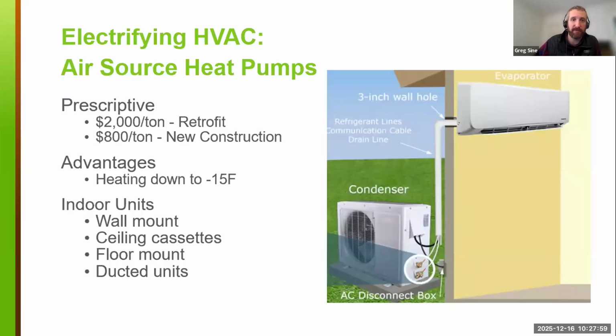They have a high efficiency, or for heat pumps, it's evaluated with a coefficient of performance. So you might hear COP; the higher the COP value, the better. So that's a good key term to understand. It can be applied for a variety of buildings. You could do very small buildings with this type of technology, or larger buildings, like entire schools, could be retrofit with air source heat pumps. For smaller projects up to 150 tons, there's prescriptive rebates available, both for retrofit and new construction programs. For larger projects over 150 total equipment tons, we could look at it potentially as a custom project.